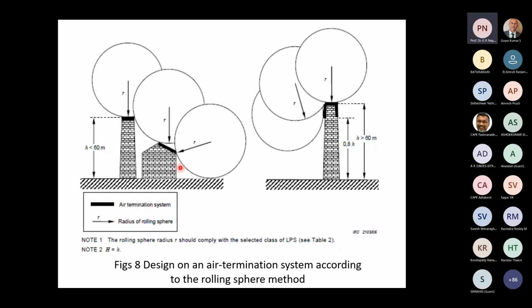Now, supposing the building is taller than 60 meters, as shown in figure B, roll the sphere completely on all the surfaces, but you'll find that we need a lightning protection system on the top area, for which you can use either the geometric method or the electrogeometric method, as the case may be. And on the side, roll it only to a height of about 20% of the height. That means if the height is 100 meters, down to about 20 meters here. So this much needs protection. So this much will be mesh or sheet or closely spaced mesh. The broad meshes, as I mentioned, 5 meters by 5 meters or 10 meters by 10 meters, certainly will not give the required level of protection.